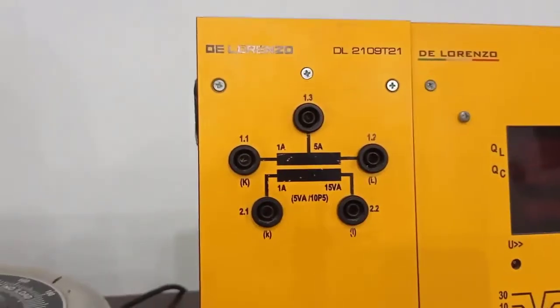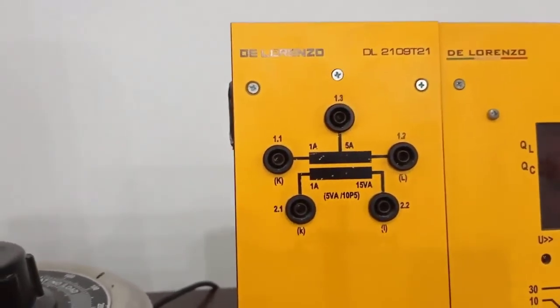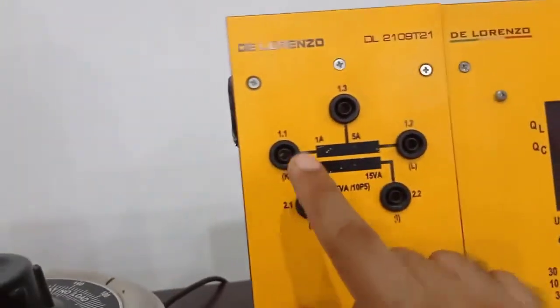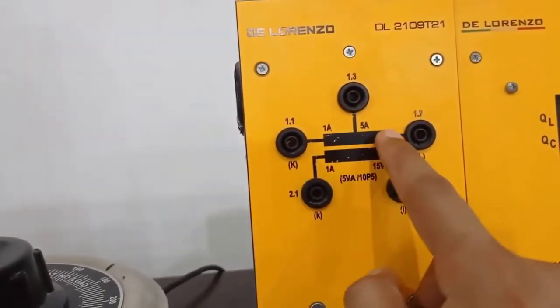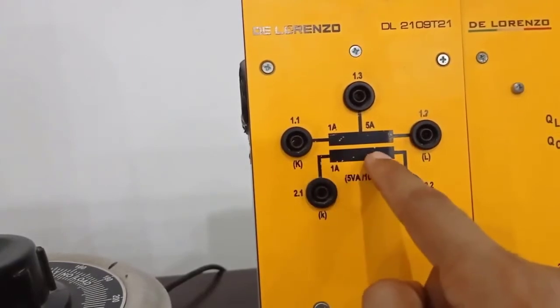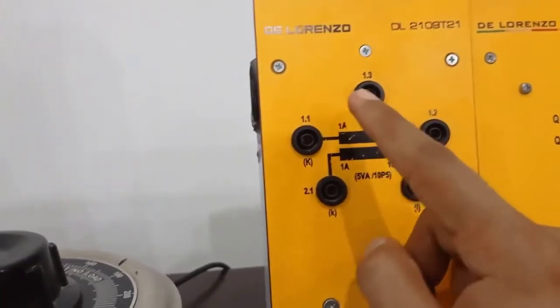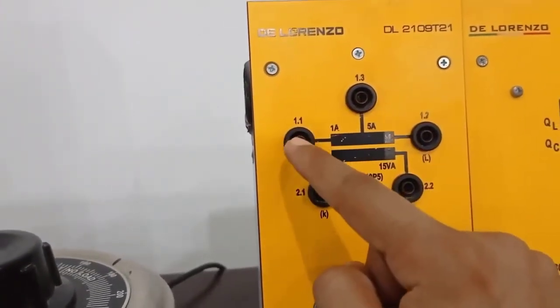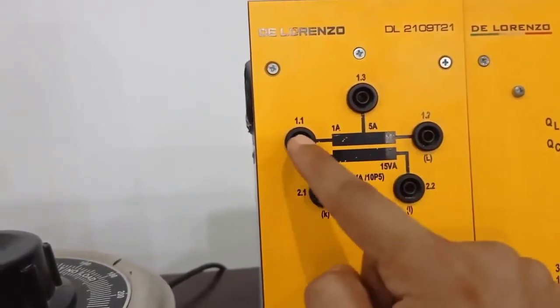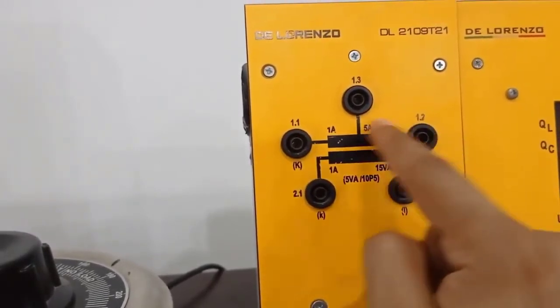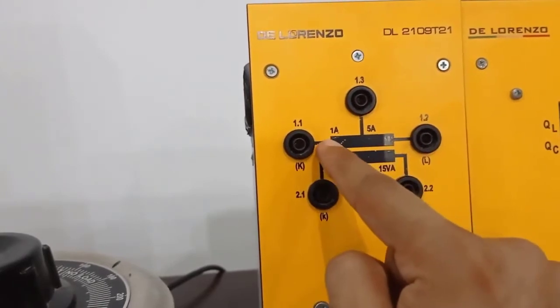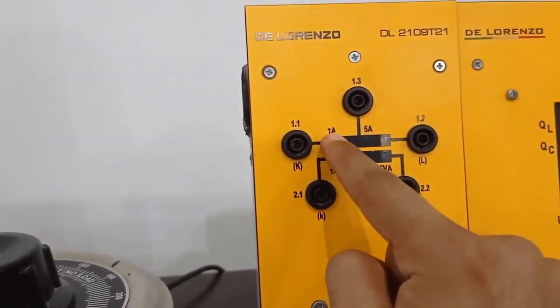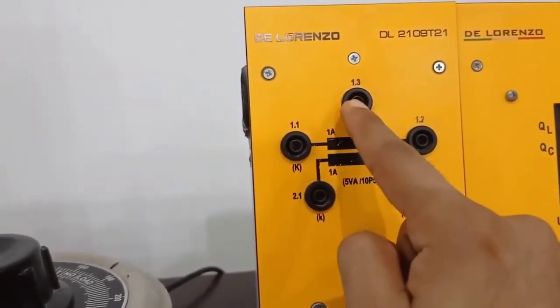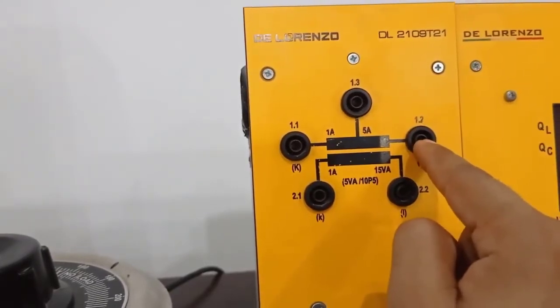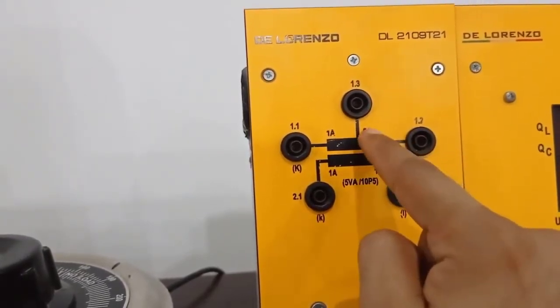Here, this is a CT, a single phase CT, that will be used in this experiment. It has two windings, primary winding and secondary winding. There are multiple ratings available for the primary winding. If we use these two points 1.1 and 1.2, between these two terminals the rating of the primary winding is 1 ampere, and if we use these two terminals 1.3 and 1.2, the rating of the primary winding is 5 ampere.